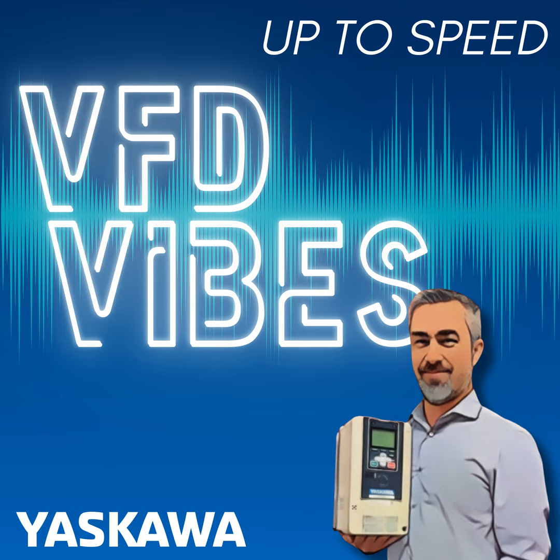So if you wanted to go to our website and type in programming simulator, what you would find is a handful of simulators that would be able to simulate our product through software and actually present you with the keypad interface, the I/O, and allow you to go in and virtually press the buttons on the keypad to become familiar with it, wire the I/O, even test out some parameter settings in programs. And that programming simulator can output a settings file that you can then import into our programming software and then program the drive directly from your simulation.